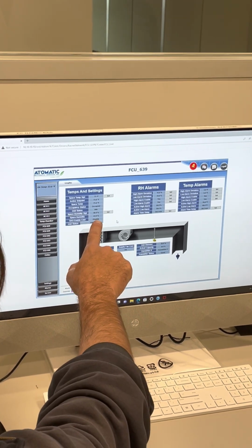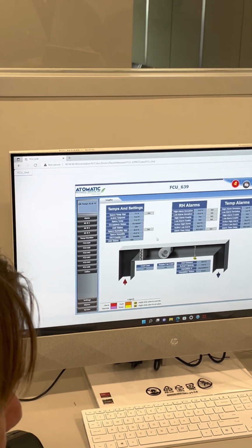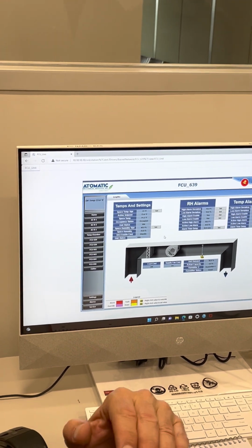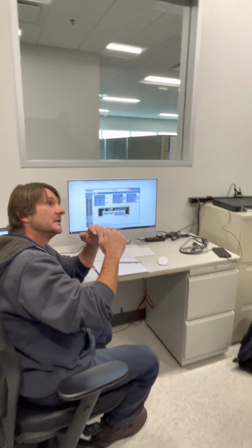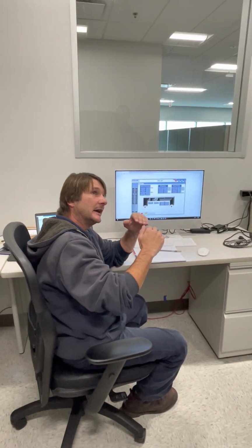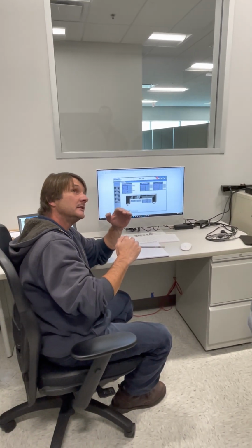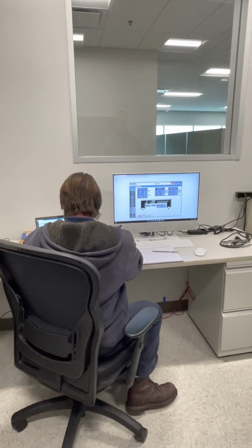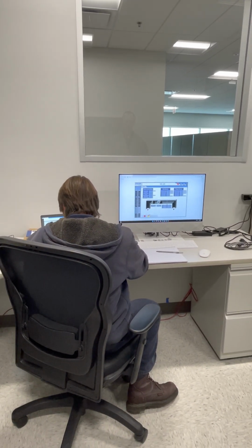So you see, actually, hold on, let me pull it up here. When we were running into a few of these issues behind the scenes in the BAS, what I did is I monitored the space humidity and what the set point is. And I did a trigger in there that if the space humidity got 10% above our set point, then it was going to automatically disable that humidifier, as kind of a stopgap. I did those hard numbers, and we can change it if we want to. Let me pull that up real quick.